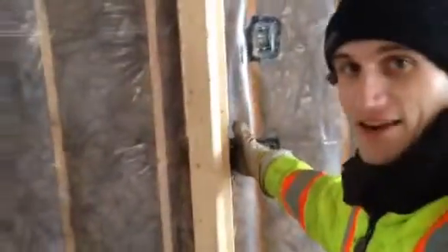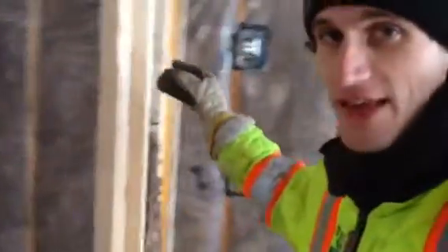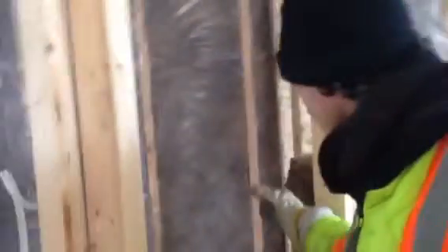And as I was talking about in a previous video, with this area being a heated space and this being unheated, cold space and insulation here, we talked about how the insulation would be getting wet because of the condensation that would be happening in here. The thing to do is to stop the air from getting to the insulation, to stop the vapor from getting to the insulation. Obviously, it's a vapor issue because it's the airborne water that gets in there and then condenses and causes the problem. So that's why we call it a vapor barrier.